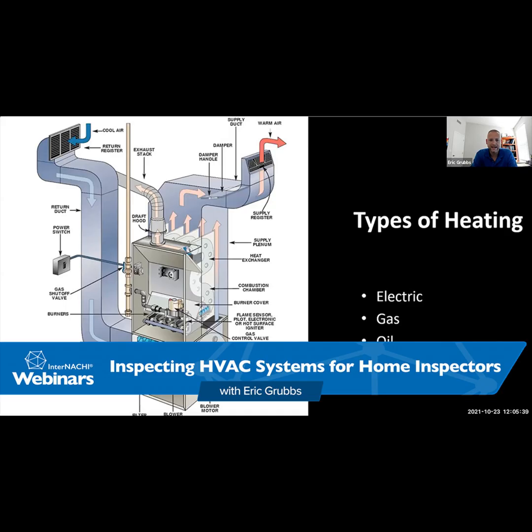And now here's a picture. Go ahead, James. That shouldn't be resting on the concrete, right? We should be lifting that up and have it underneath it. You are correct. It's interesting to find a lot of pictures where systems were not installed properly. As you can see, you definitely have a coil on the top end of that furnace for the AC section, and it should be suspended and secured properly, along with probably an external or emergency drain pan, to keep anything from damaging underneath that home.